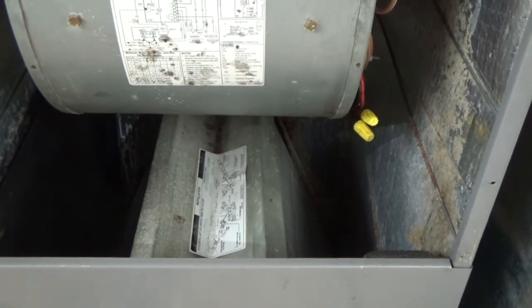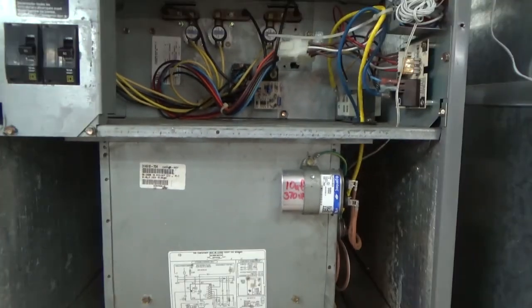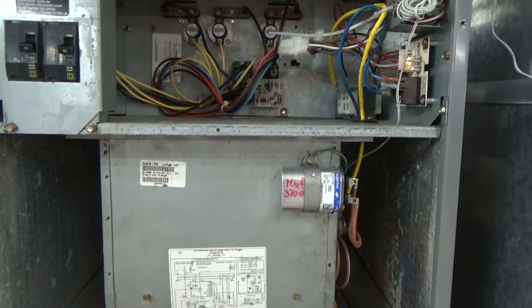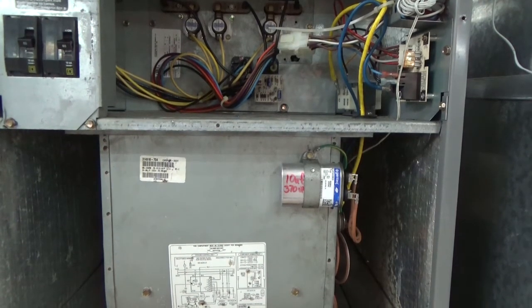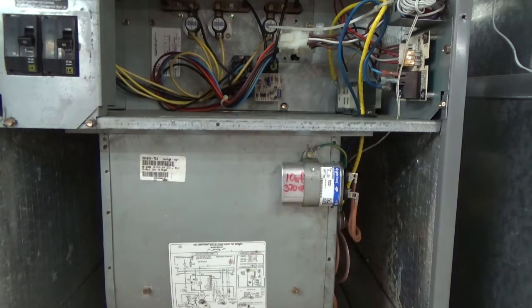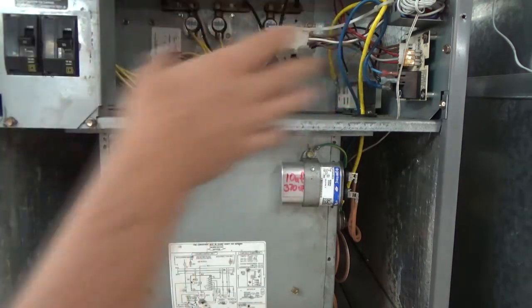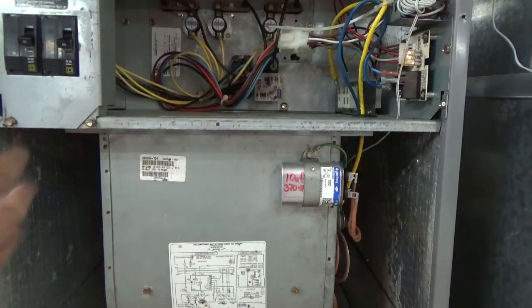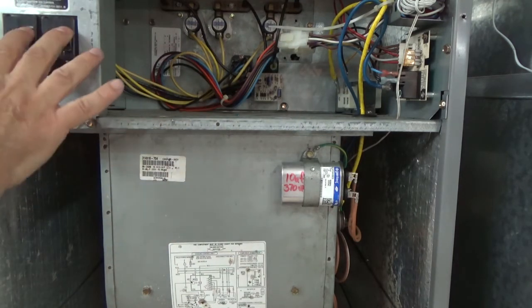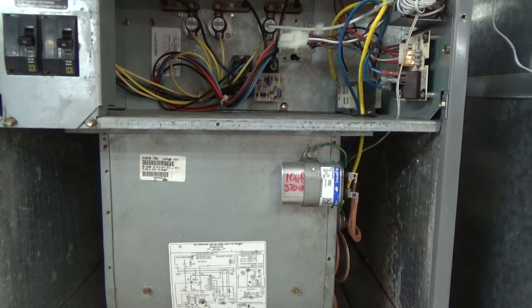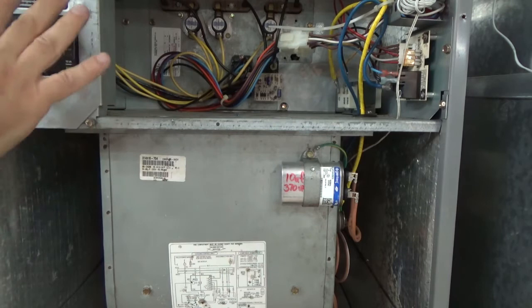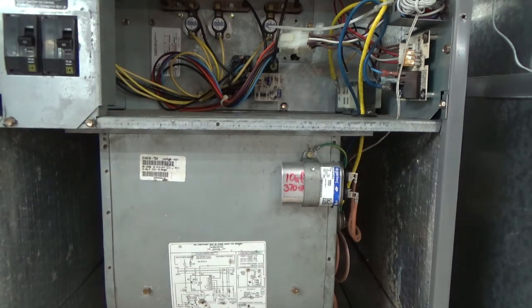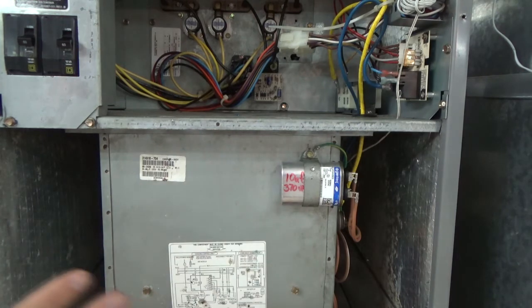So we're kind of done in here in the inside air handling unit, so we can put the panel back on. So again, make sure your hose is clean, your filter is clean if you have one. Make sure there's no mold growing on here. Lubricate your fan if you can, if you want to. Make sure all your electricals are in good shape, nothing shorting out somewhere, you don't see marks anywhere. Make sure your breakers are okay, meaning that they function. So you've turned them off, you'll turn them back on, the unit will come on. Just kind of visually inspect everything. Just get familiar with it, inspect it.